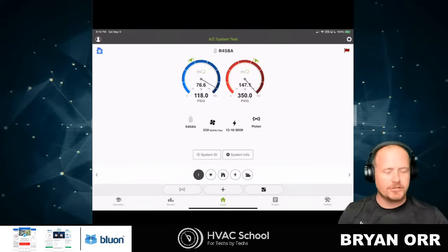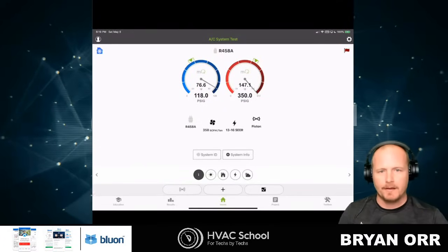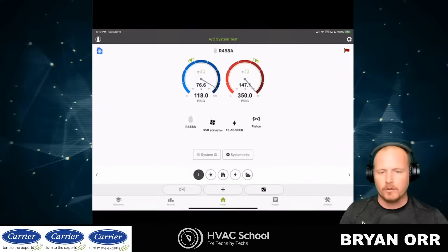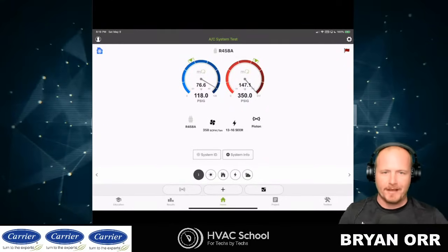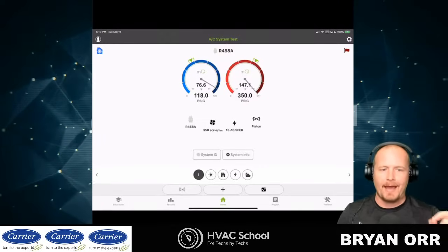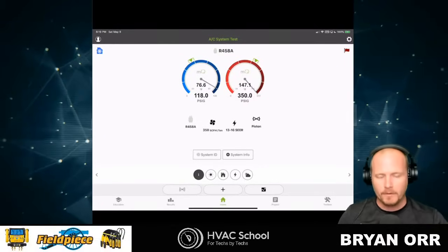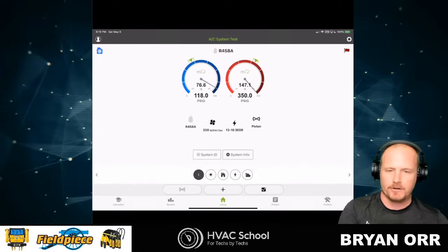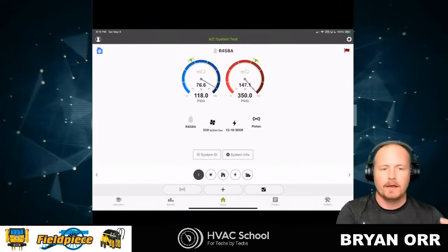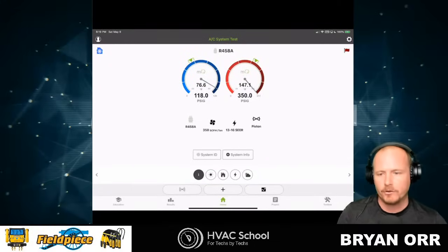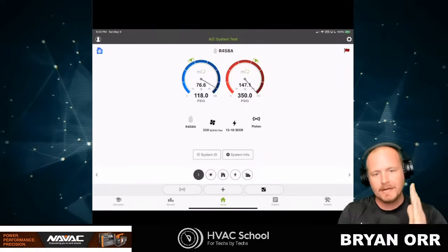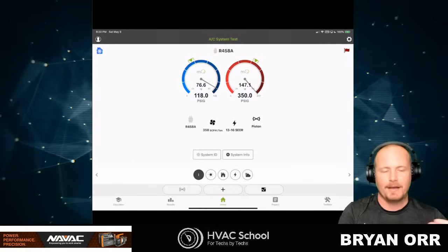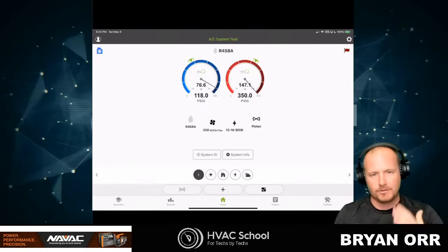Yeah, and I just changed to a TDX20 R458A just to show that that's a high glide refrigerant. Of course, the pressures aren't right for that, but it's going to look at the center, and it's important because we're talking about average coil temperature, which is something I talk about a lot. When you have a high glide refrigerant, you care about dew point and bubble point, which are the edges, but in terms of how the system is going to operate, you really care about that average coil temperature.